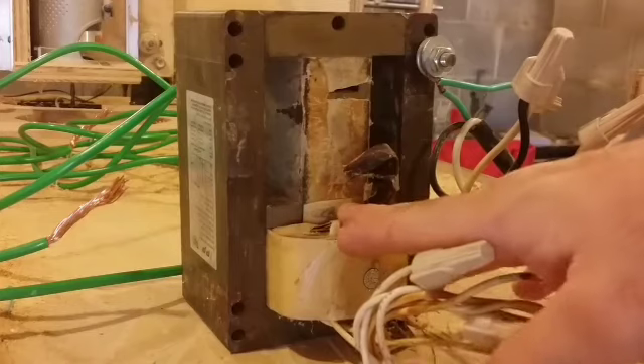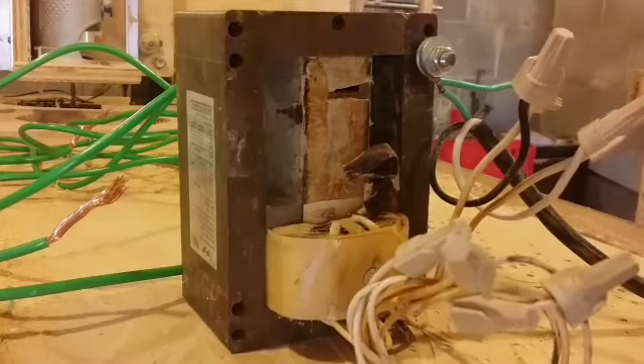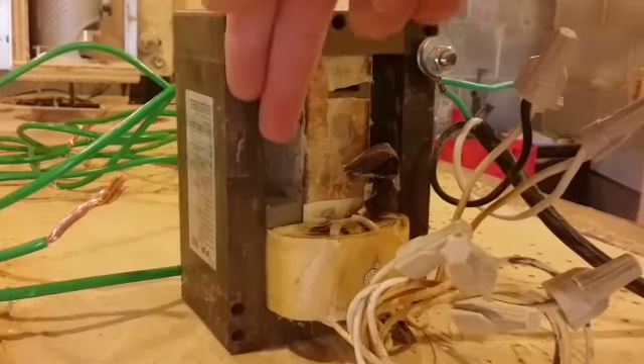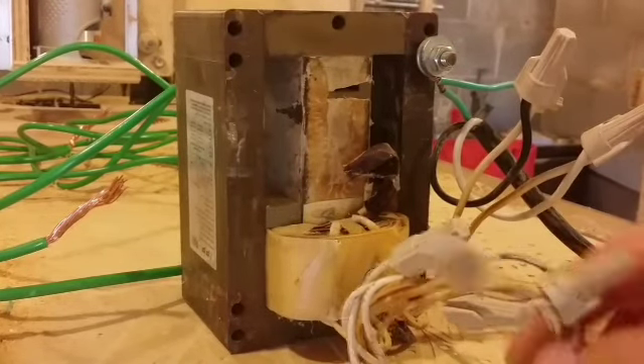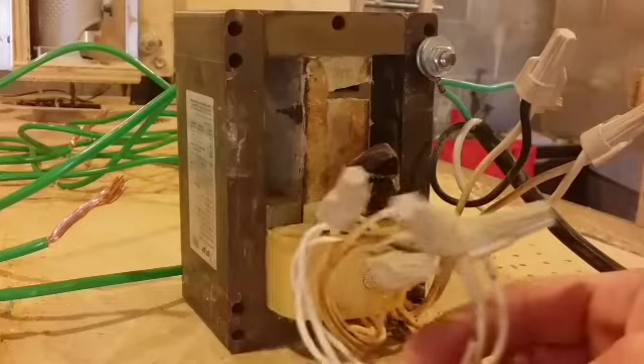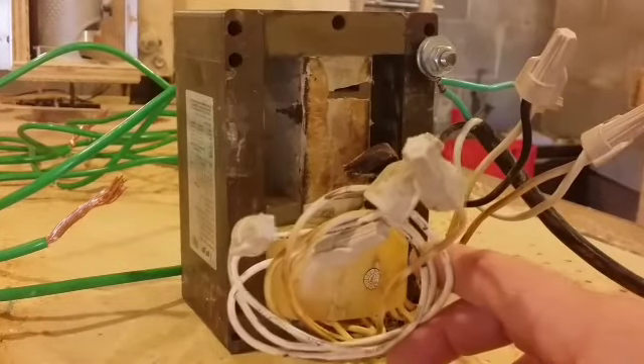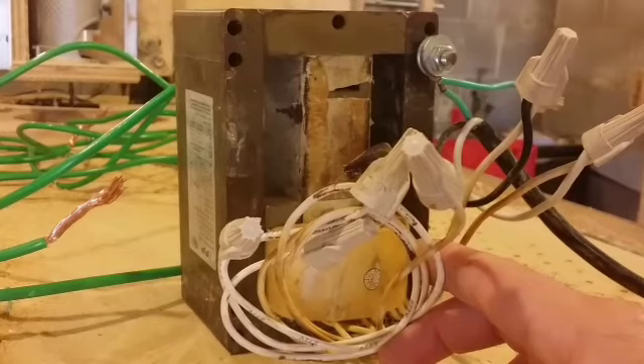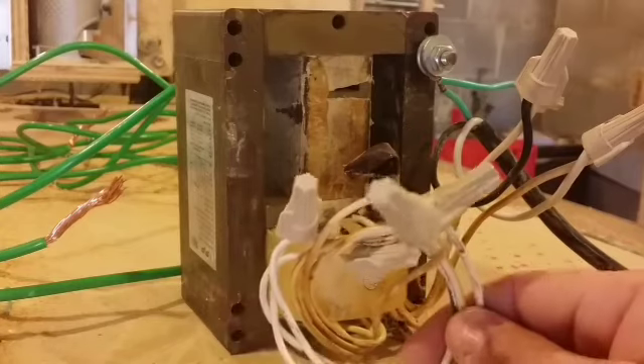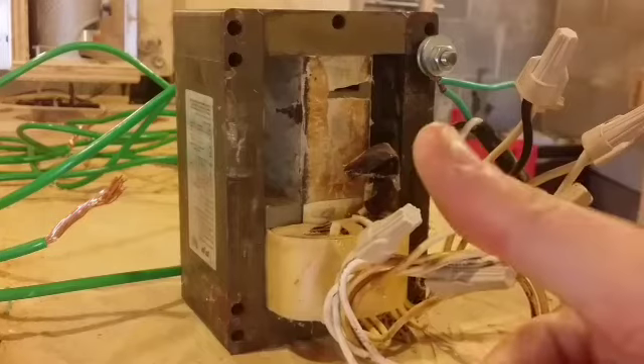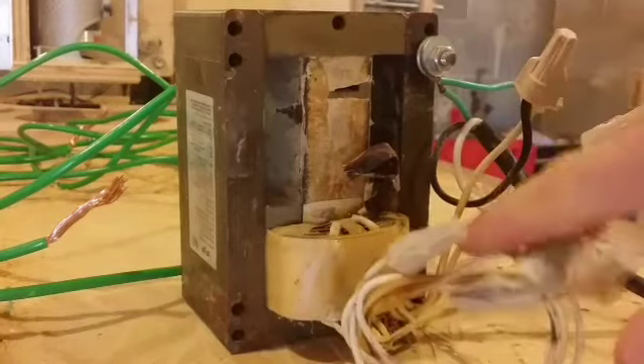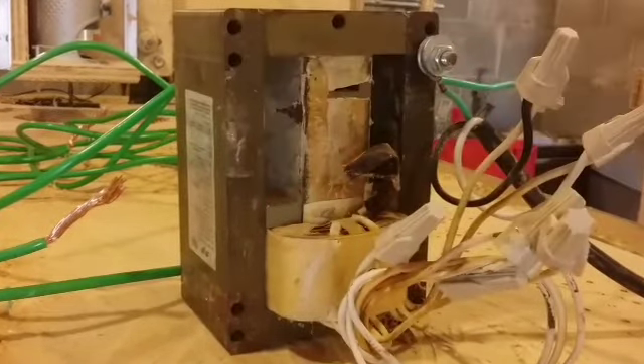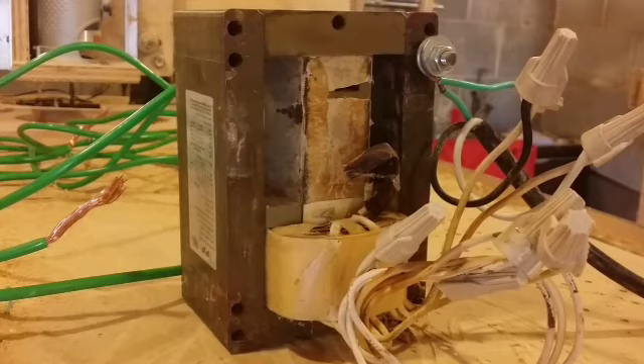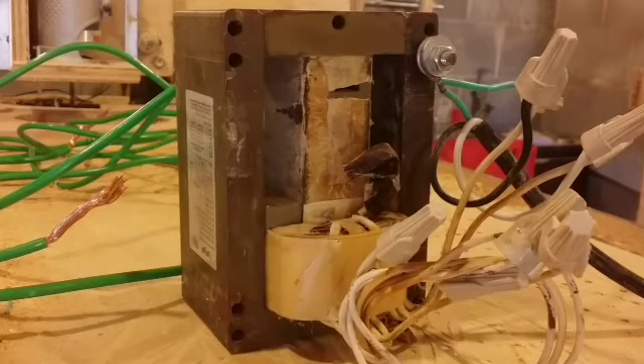The primary's in fine condition, and I realized this could be used as an auto transformer because of the multiple voltage taps. In other words, you can hook this transformer up to multiple voltages depending on what you have on site. There's 5 taps in here: 120, 208, 240, 277, and 480. And the higher the voltage, of course, the less current it will draw for the same amount of watts.